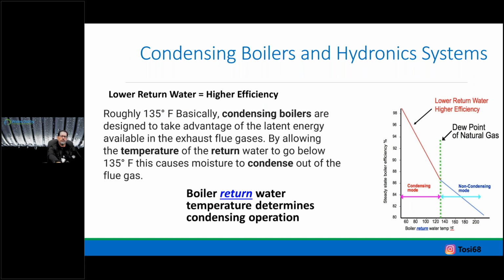Again, talking about lowering water temps. So what is that point where we do best? And that's basically about 135-degree return water. So imagine right now on the system side, not the boiler side, we have in our mind a high number, 180. And if it comes back at 160, that 160 mixes with the closely spaced tees, hydro-sep, or low loss header or something like that, back to the boiler. So I'm now engaging the burner to about 160-degree water. It's going to do something, but not everything that it's engineered to do.